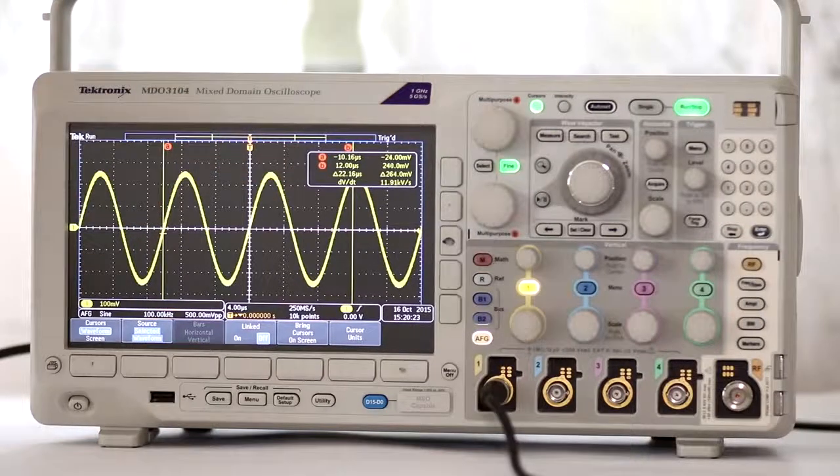In the left column, labeled A, top line, the absolute value in microseconds changes. The second line, labeled B, does not change because it is the exact value of the right-hand cursor, which does not move when you turn multipurpose knob A.